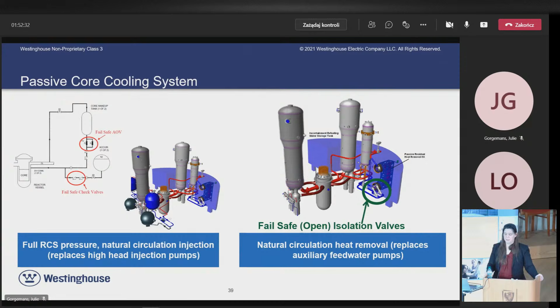In AP1000, like all our passive safety systems, what we need is a one-time valve movement. We designed those valves so they will automatically open even if we lose all power at the plant. We need power to maintain them closed, using solenoid valves and things like this. So you design your valves to require power to stay closed, meaning if you lose power, they switch to the open position and your safety systems activate.